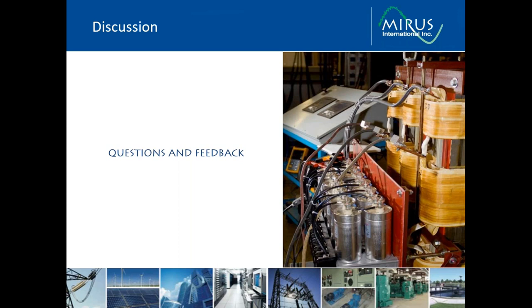Okay, we had a question about the slide that showed the six pulse waveform showed 80% of the harmonics in the fifth harmonic and referenced the 1 over H relationship that was listed. Okay, yeah, that relationship is more of an approximation. I should actually show an approximate symbol rather than an equal symbol in that slide. The exact magnitudes will vary dramatically, depending on whether the rectifier has an input line reactor or an output DC link choke, whether the power system impedance is high, a weak system or a stiff system. All of those things factor into the actual harmonics that are being drawn at each frequency.